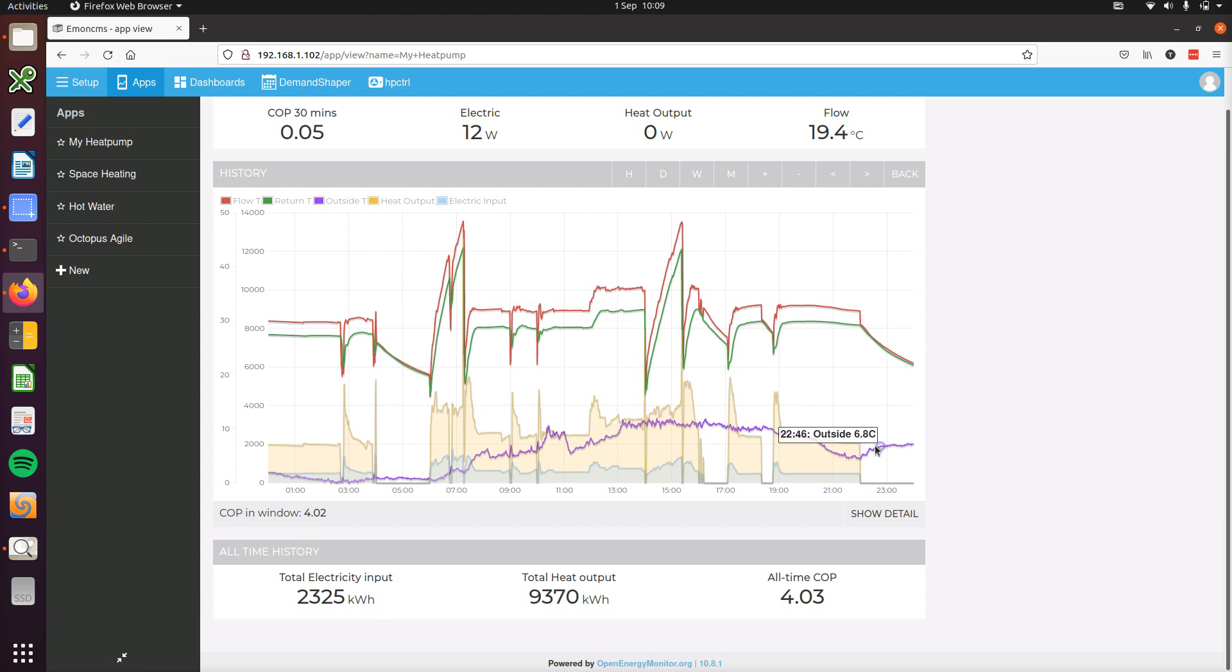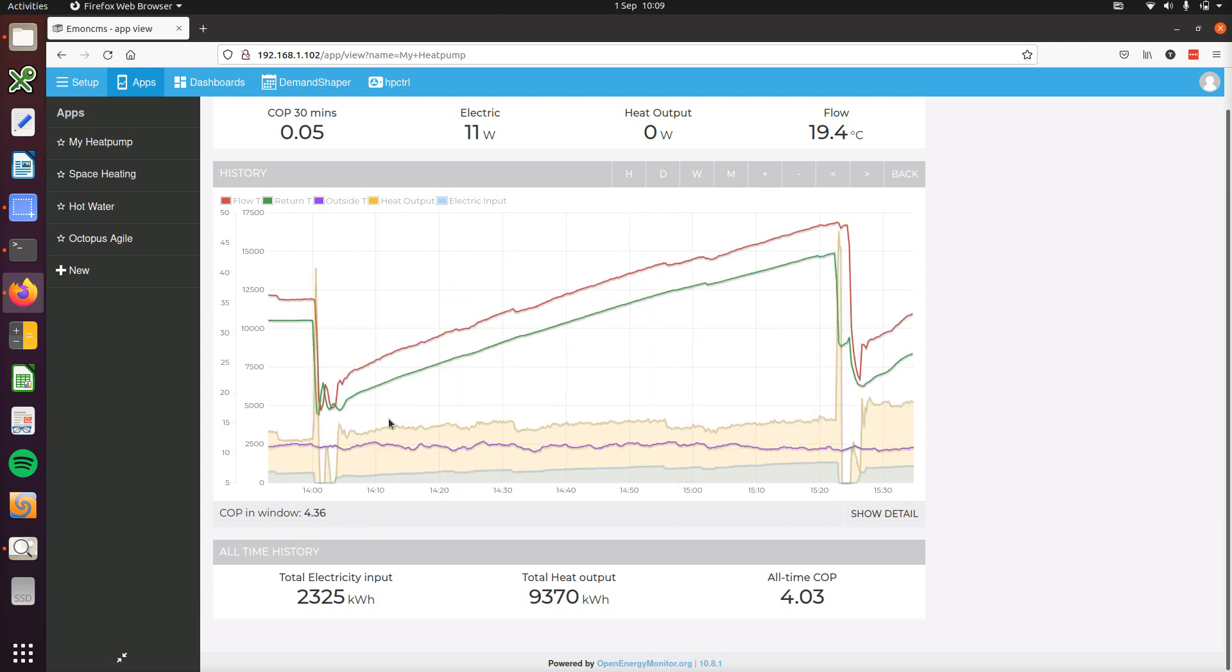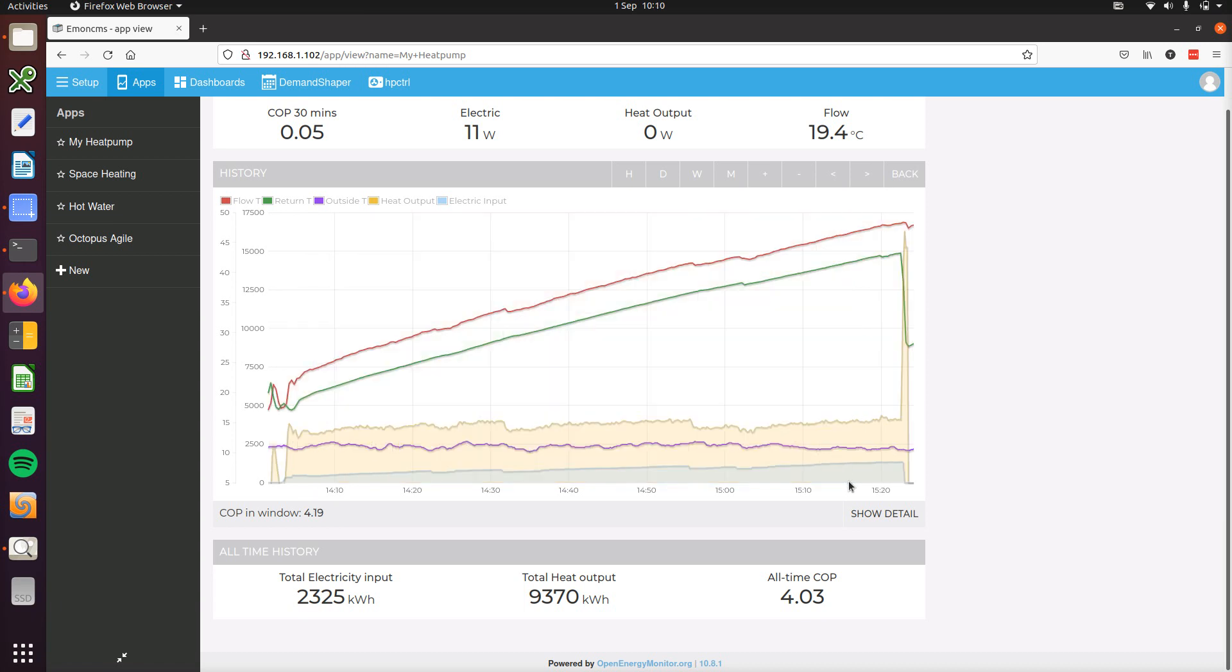The COP for the selected period is again shown here at the bottom and we can zoom in on a particular period to see the COP for that specific period, so I'll zoom in on this hot water heat up cycle. That's a COP of 4.2.